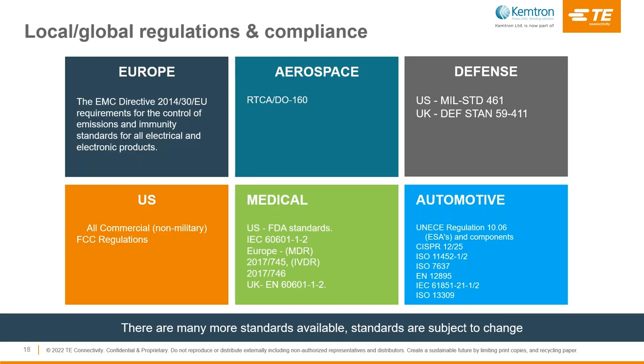There are many EMC standards and regulations in existence, and the applicable standards will depend on the type of equipment and the country it will be used in. In Europe, the EMC directive specifies requirements for the control of emissions and immunity standards for all electrical and electronic products. In the US, all commercial non-military electronics are subject to FCC regulations. For military products, in the US the standard is MIL-STD-461, while in the UK the standard is DEFSTAN 59411. It is important that you understand the EMC requirements you need to achieve for your specific application.